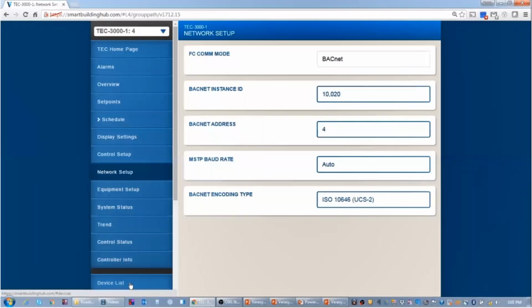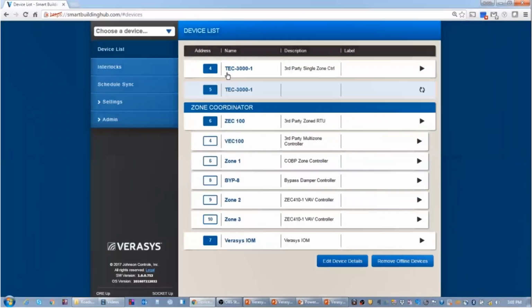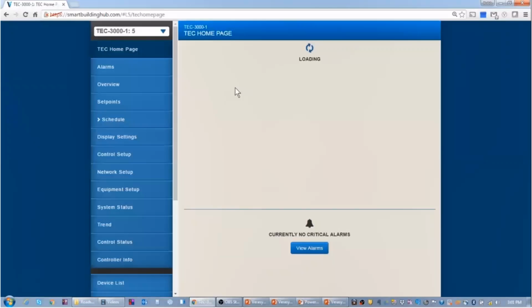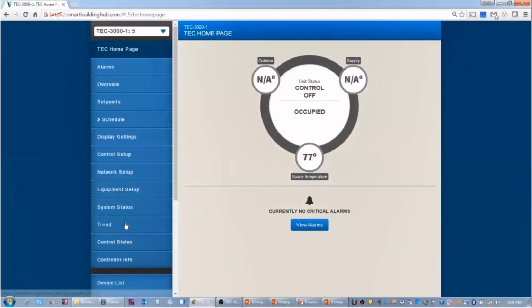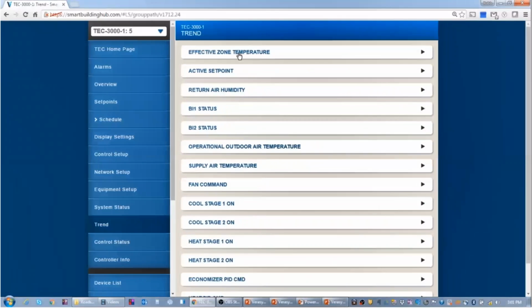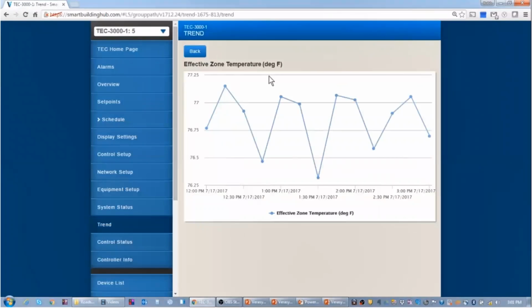When you go back to your device list, you can see the TEC now shows up on network 5; it goes offline on number 4. After making this change and giving it an entirely new address, you can go back in and see that all the data still comes in the same—all the view definitions are still there, all the trends are still there. You can even take this device off the network and put it on a different trunk, and all the data will still be there.